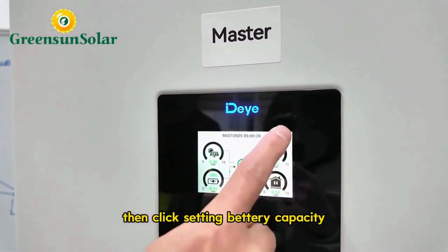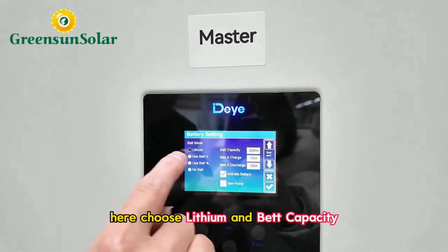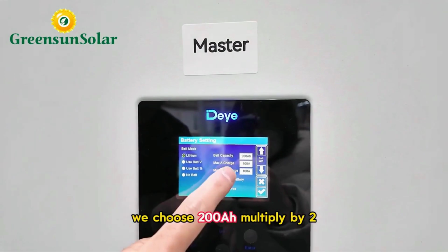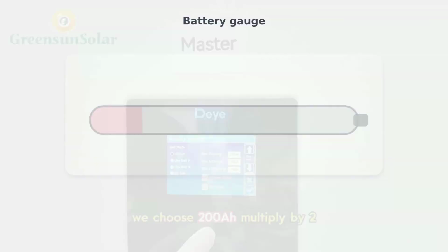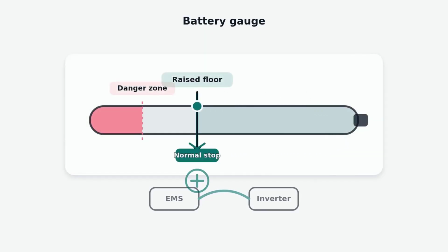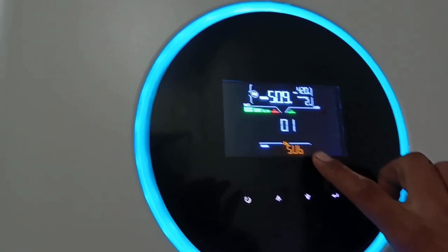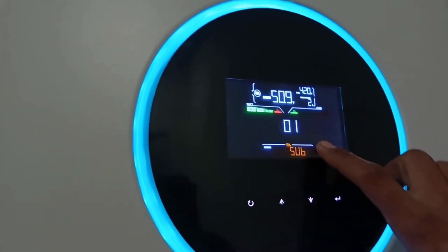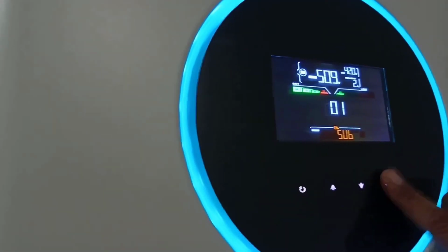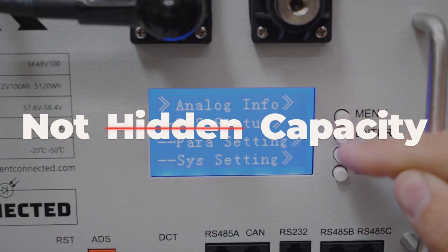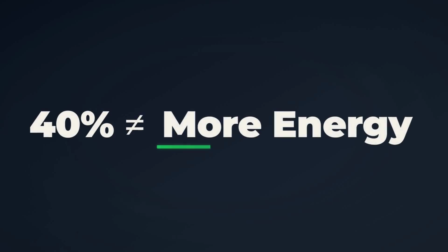This setting is supposed to stop the inverter or energy management system before the battery management system is forced to intervene. The BMS disconnect is an emergency brake. The discharge floor is a speed limit. You want the speed limit doing the work, not the emergency brake. Here is what it actually saves, not hidden capacity. The battery does not suddenly have more power because you changed a number.